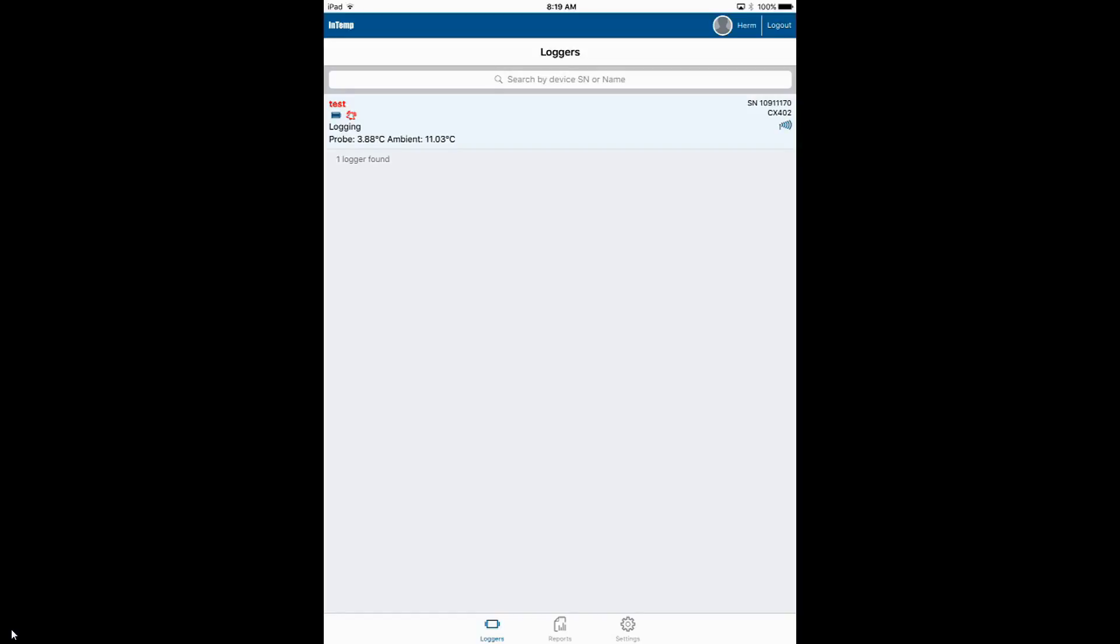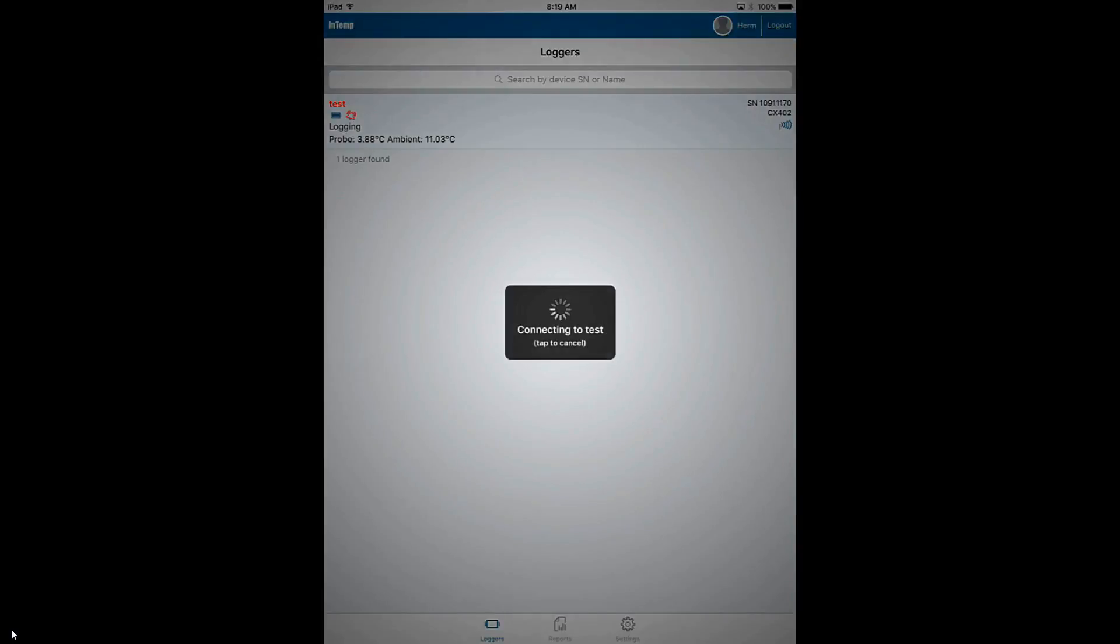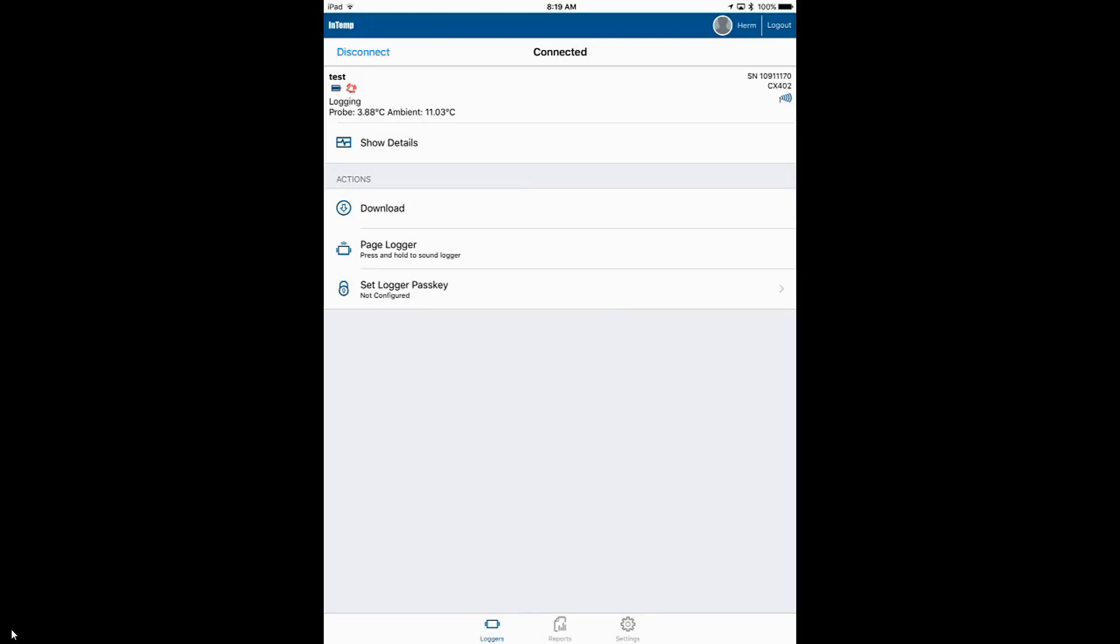To download the data from this logger, we'll tap on the name of the logger. We will connect to it and then we will tap on download. We have three choices: download and continue data logging, download and restart the logger with the same configuration, or download and stop the data logger.